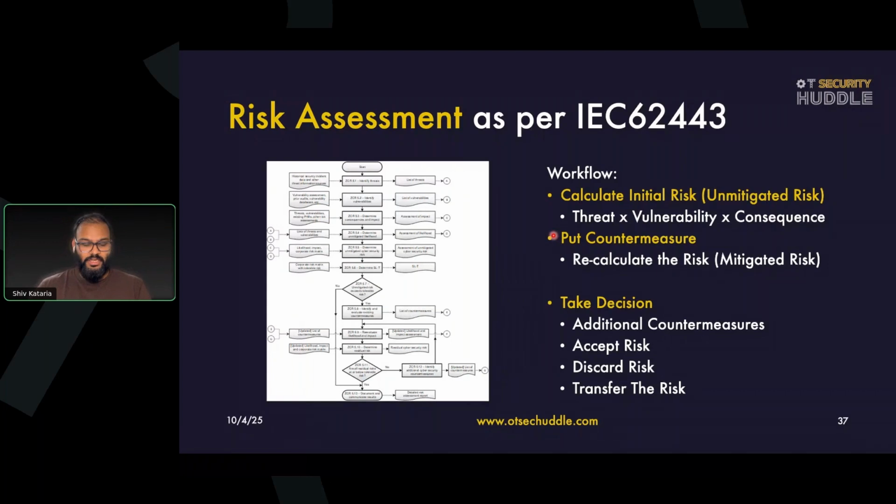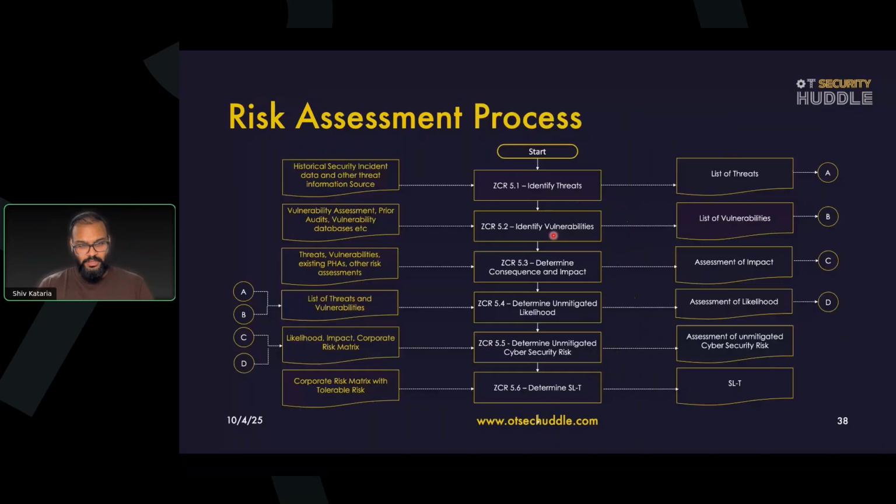the risk assessment exercise. Like the same example, there is a vulnerability in your power plant, and a new threat group has designed a specific malware. There are possibly already some mitigation measures. But when you have identified a new threat, it is also having your assets possibly getting impacted. Then you would see what is already there, and what additional countermeasures you would put in place. And then you take a decision whether you want to accept this risk, discard that risk, okay, this is not applicable to us, or transfer that risk by buying insurance or possibly engaging a managed service provider or something like that.